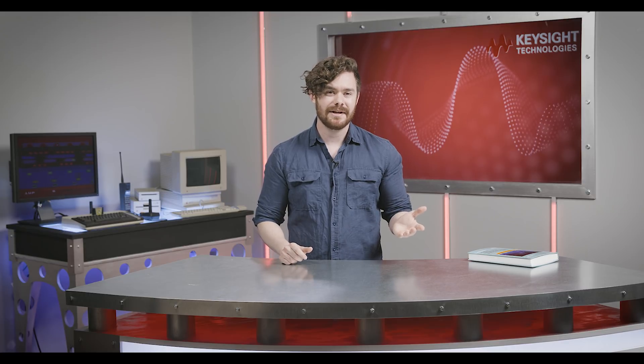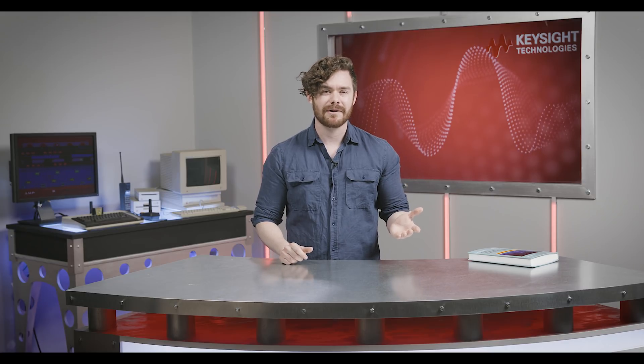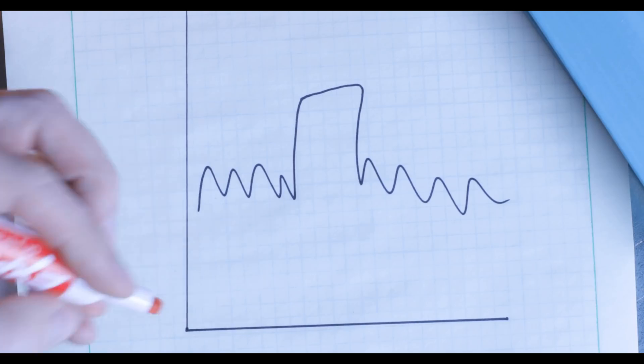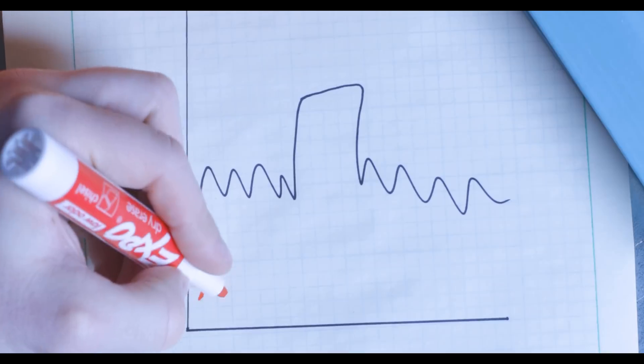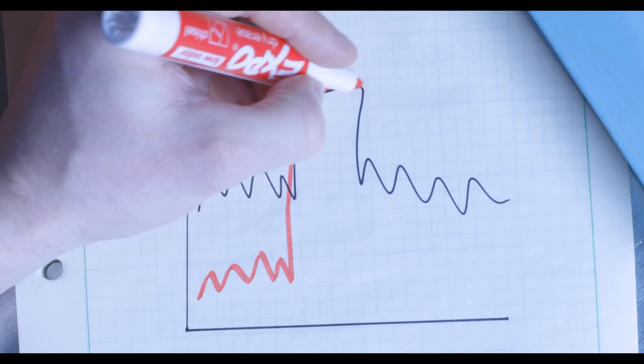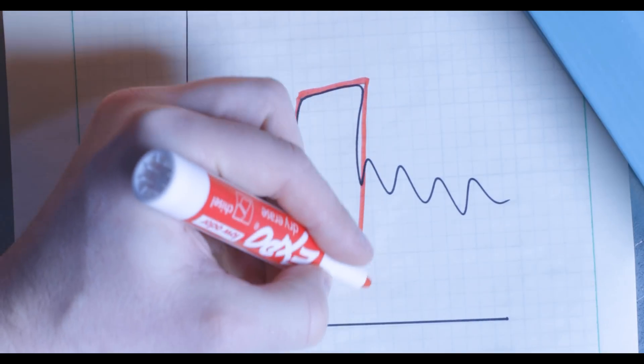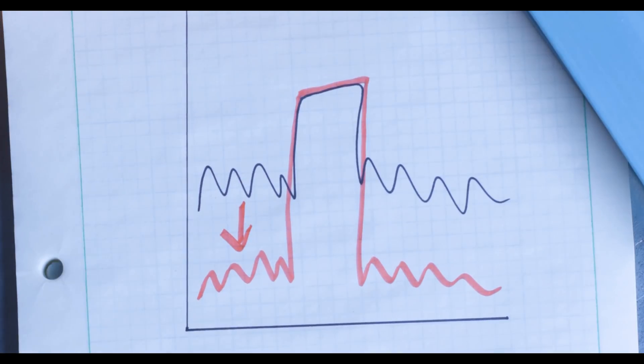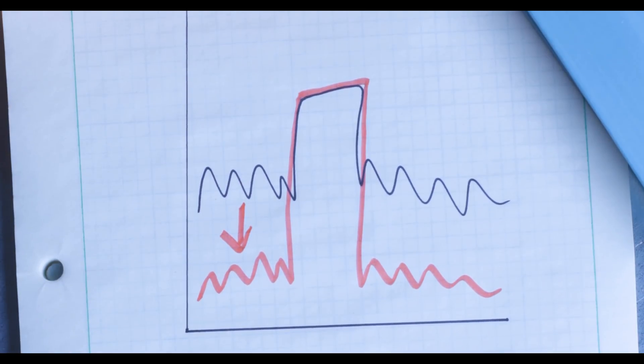If you can't increase the signal power, the next best thing to do is to reduce the IF bandwidth. This will make your network analyzer process smaller chunks of the measurement, so you'll get a more accurate result, but the measurement will take longer.